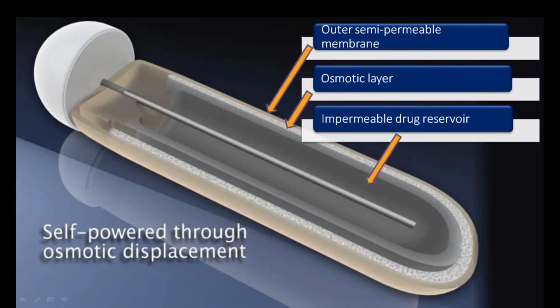The flexible reservoir is composed of a synthetic elastomer, which is chemically inert to most drug formulations and is impermeable to the material in the surrounding osmotic layer. The osmotic layer in the middle contains a high concentration of sodium chloride that provides the osmotic driving force. And the outer rate-controlling membrane contains a proprietary formulation that allows selective water permeability. An additional component of the pump is the flow moderator, which is a 21 gauge tube with a plastic end cap, which prevents random drug diffusion and ensures that the delivery profile is osmotically controlled.